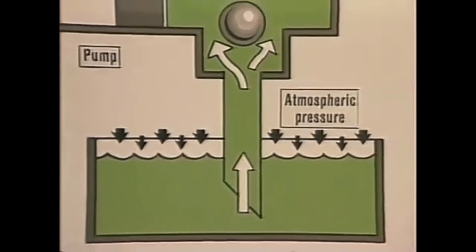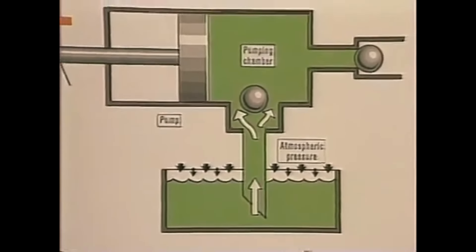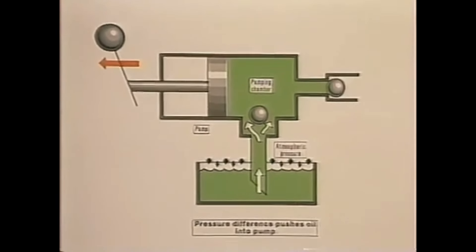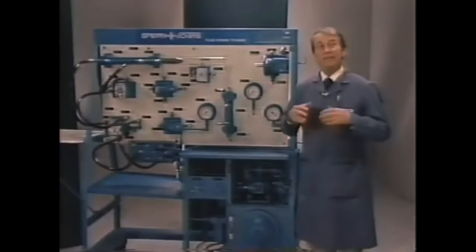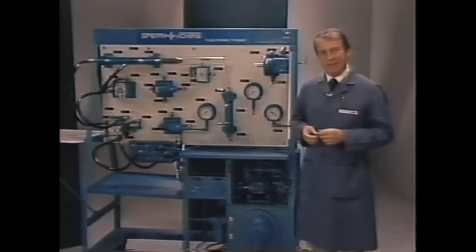It doesn't. A pump merely lowers the pressure at its inlet, and fluid is pushed in by atmospheric pressure acting on the surface. Inlet lines are especially important because with only 14.7 PSIA doing the pushing, any restriction or even too thick an oil may cause the pump to starve. The technical word for this starving is cavitation, and it causes an erosion-type damage within the pump. An air leak at the inlet causes similar problems.